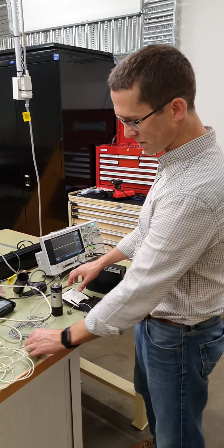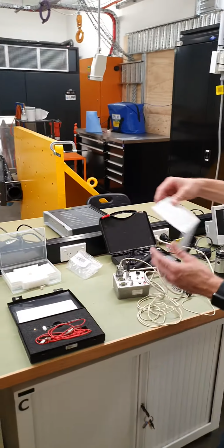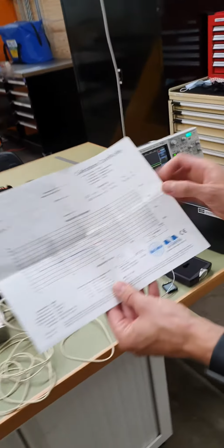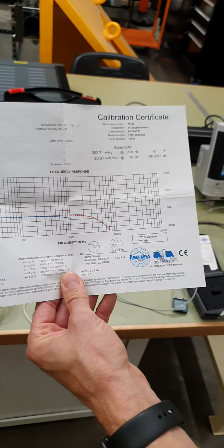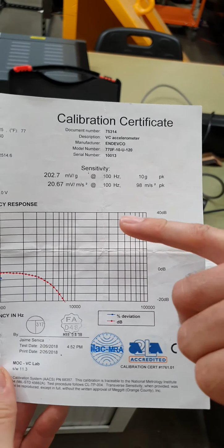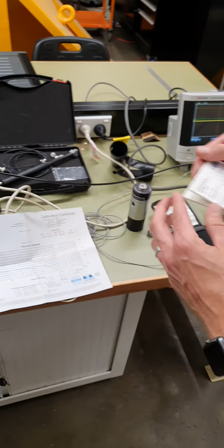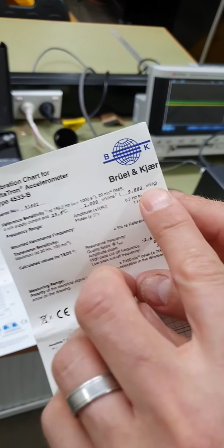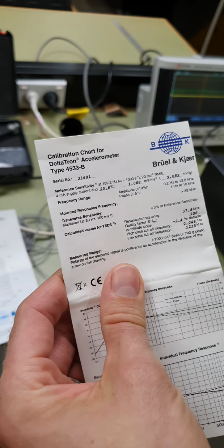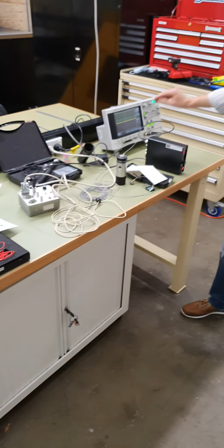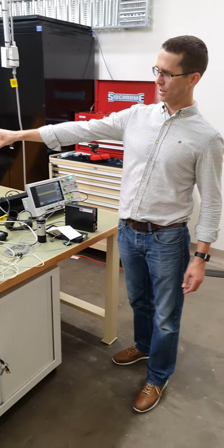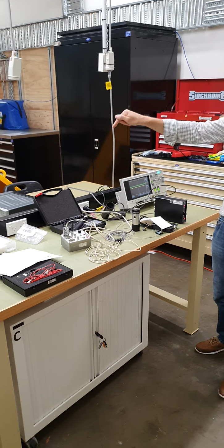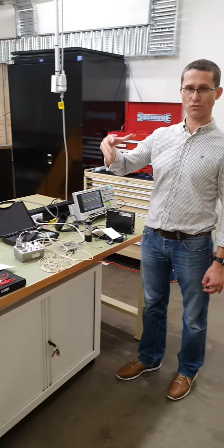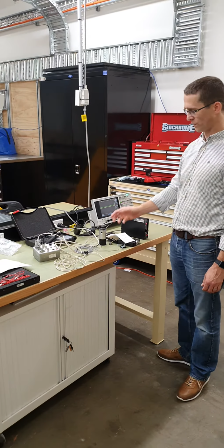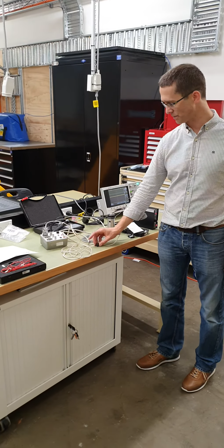They've got different specifications, they're fit for different purposes. They all come with a calibration certificate which describes their performance in terms of amplitude, linearity and phase response. They have a sensitivity in millivolts per G in this case, because this is an IEPE type of transducer. So you have to consult the calibration certificate when you're interpreting the measurements that you make in volts, either with an oscilloscope, or you can put those sensitivities into the software system that comes with the acquisition system from Siemens to be able to measure engineering units from these transducers, measurements of G or of meters per second squared for acceleration.